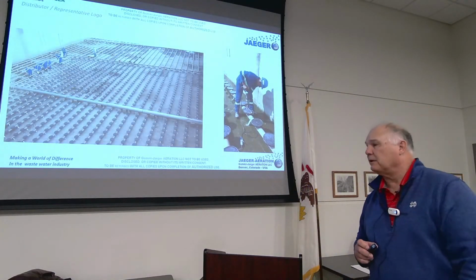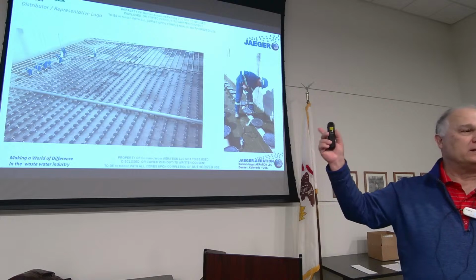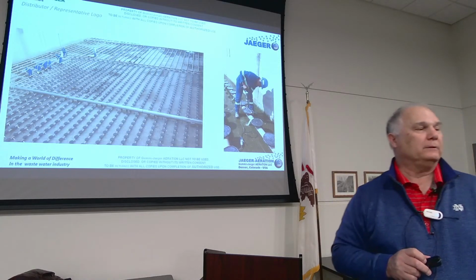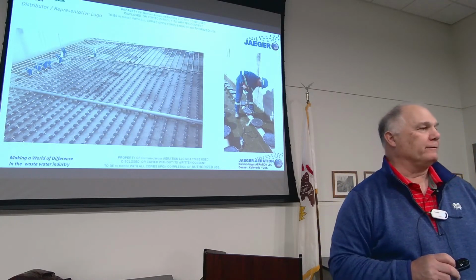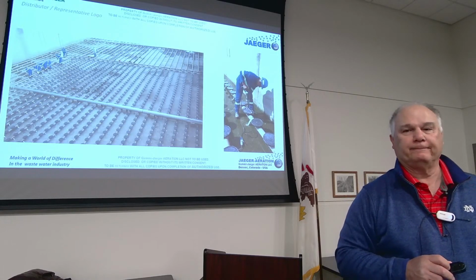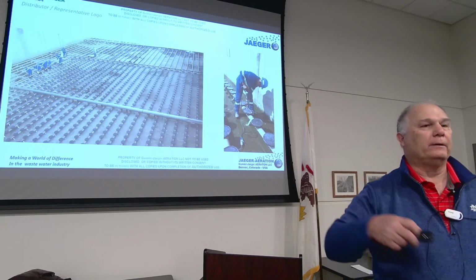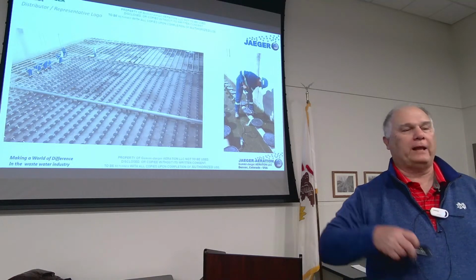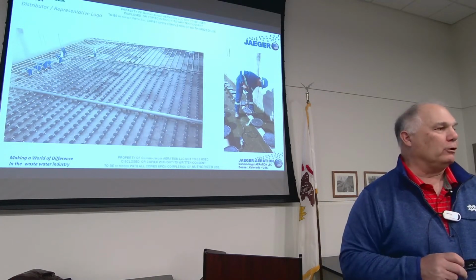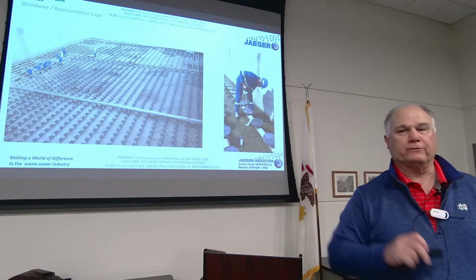So in our history, this is a standard project. 9-inch disc diffusers on the bottom of a basin, generating X pounds an hour. For every 1 MGD of flow, you're going to have about 1,000 CFM of air with 9-inch disc diffusers.